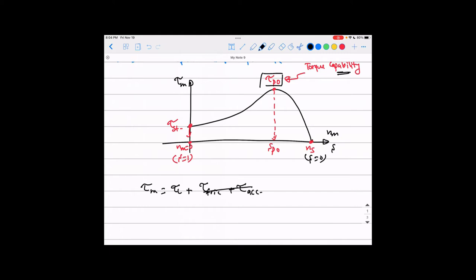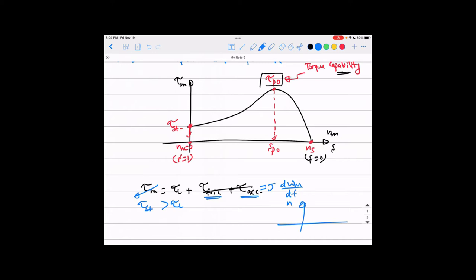The friction and acceleration terms are small compared to the load torque, so the motor torque is roughly equal to the load torque plus a little bit for friction and acceleration. The starting torque must be higher than the load torque because it also needs to accommodate the acceleration torque, which appears during starting when speed is changing. If we look at the motor speed with time, it starts from zero, accelerates, and reaches a steady state.